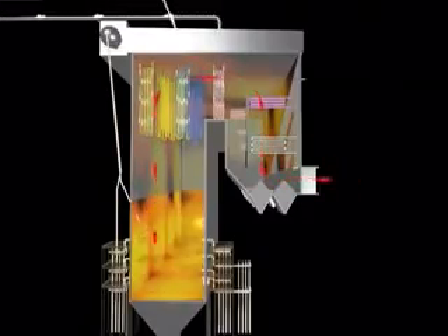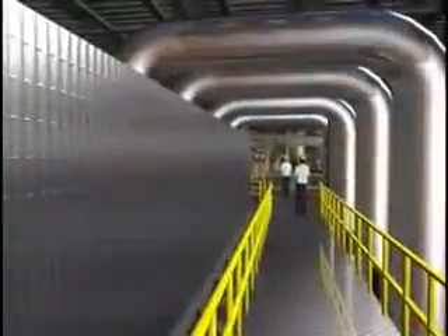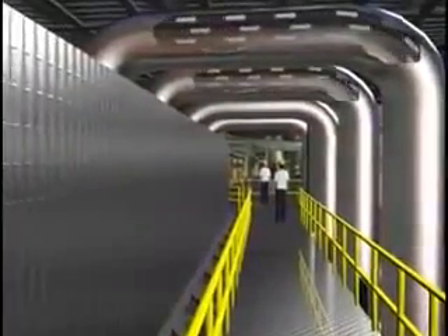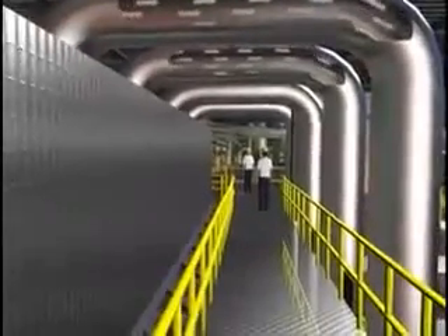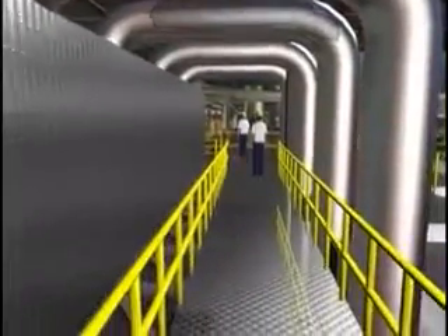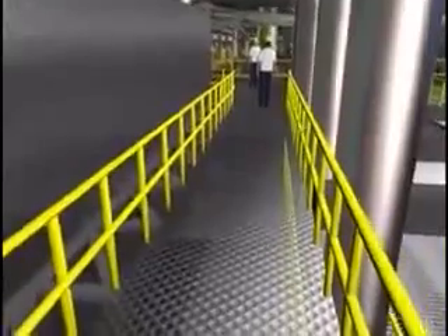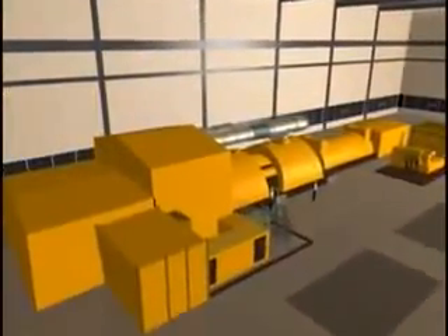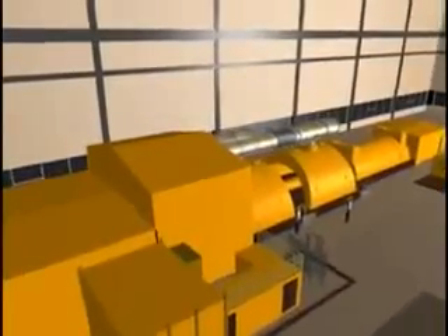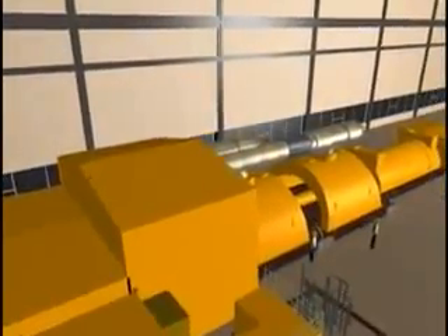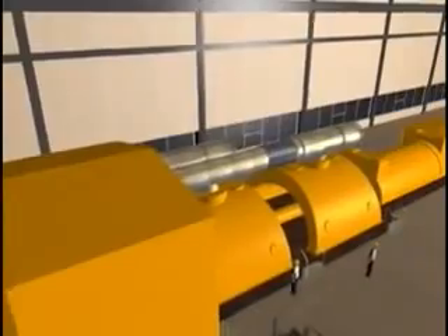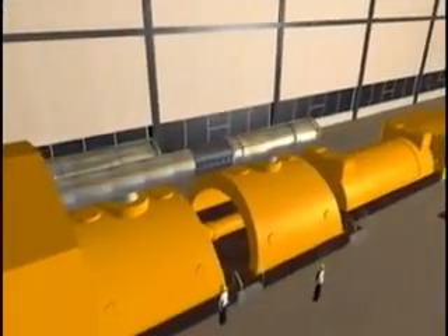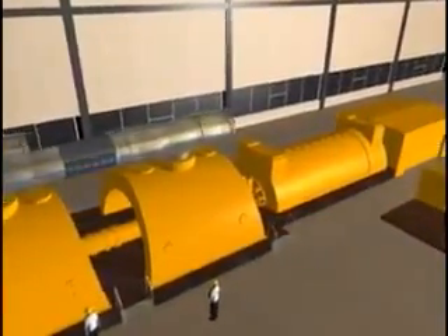This generates the thermal energy, which is transformed to mechanical energy at the turbine. The main pipe above and outside the furnace is the main steam line to the turbine. This walkway shows you the series of steam lines headed to the turbine. This turbine is the primary piece of equipment that transforms thermal or natural energy into mechanical energy that can be harnessed to provide power to homes and businesses.